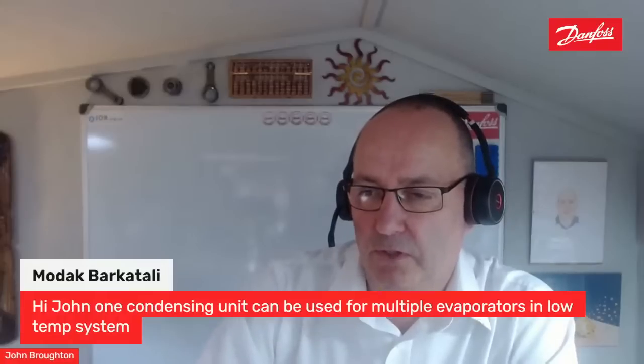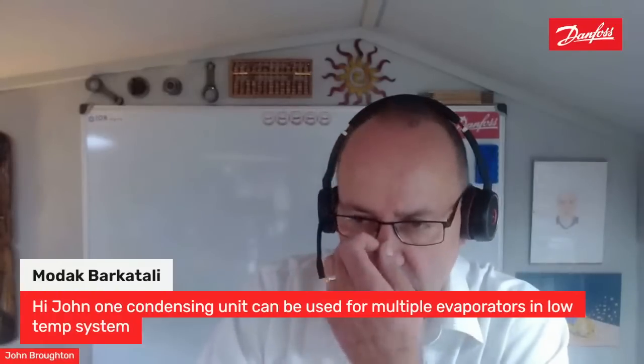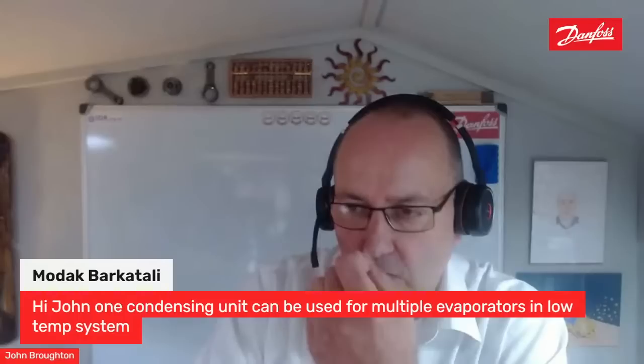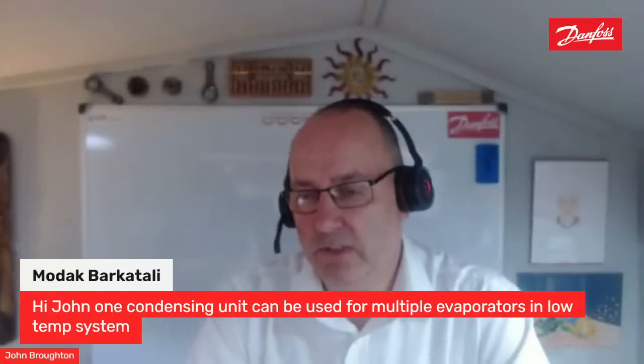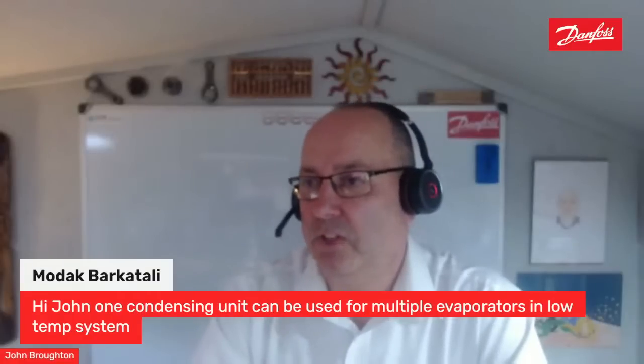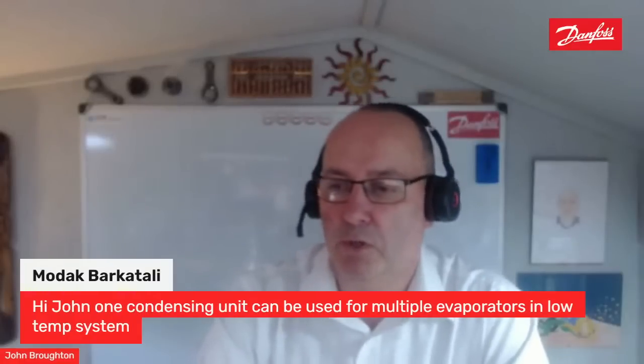Then we've got a question from Modak again on LinkedIn. Hi John, can just one condenser unit be used for multiple evaporators in low temp systems? Yes and no. If all those evaporators are in the same room and they're all on the same thermostat, absolutely fine, not a problem at all.